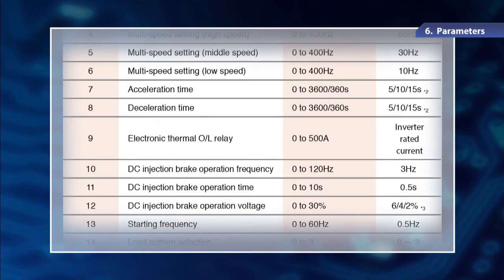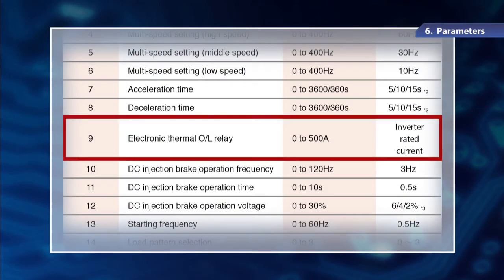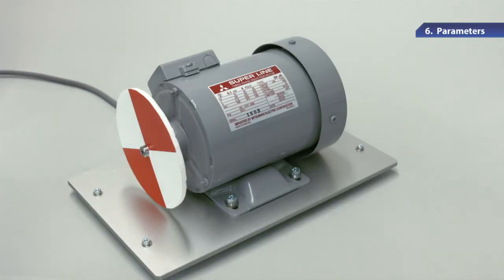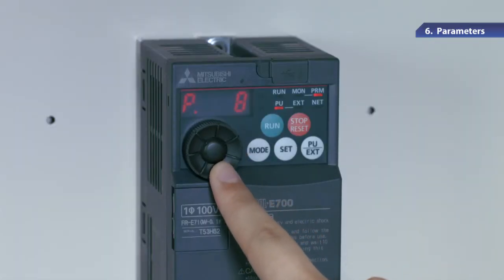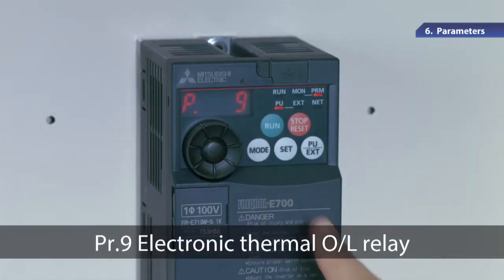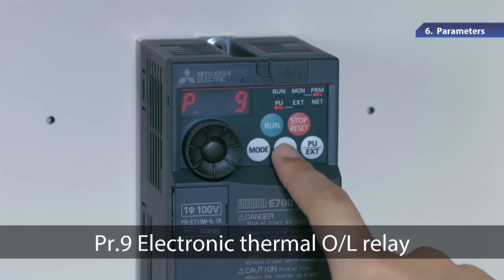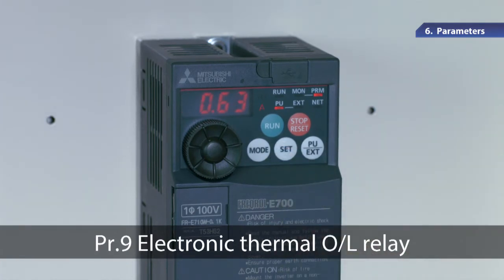First of all, let's set the rated motor current value to protect the motor from overheating due to an over current. The rated current value is the specification set to run the motor and is specified on the motor name plate. To set the value, use parameter number 9, which is for electronic thermal OL relay.